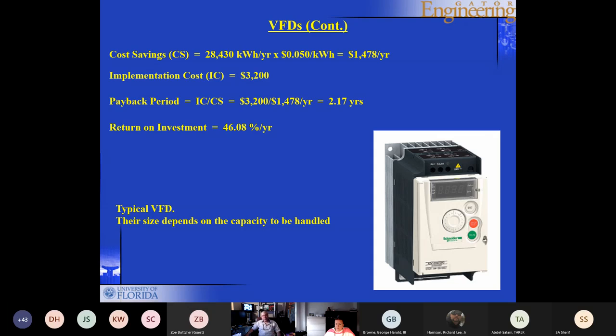If you put the implementation cost at $3,200, you're going to end up with a payback period of $3,200 divided by 1,478. You get 2.17 years. And again, the return on investment, you take the reciprocal of the payback period multiplied by 100, you get 46% return.